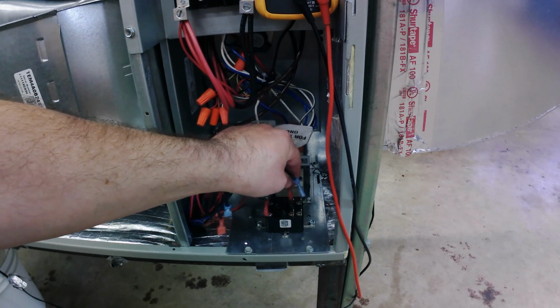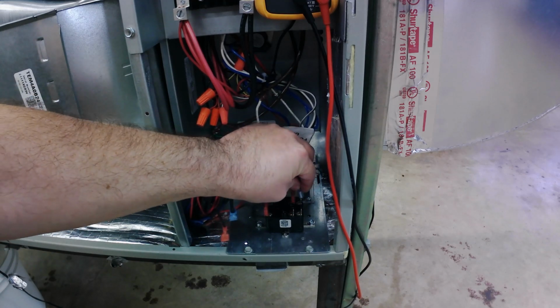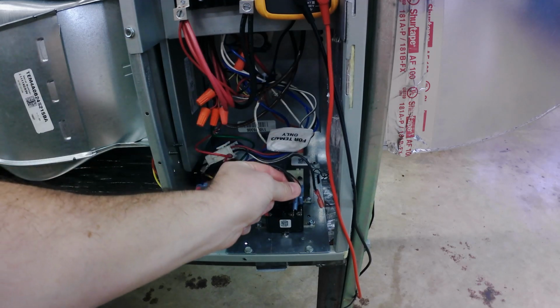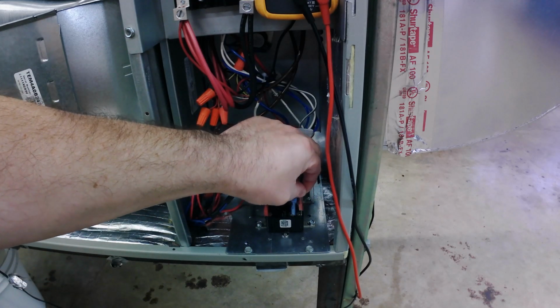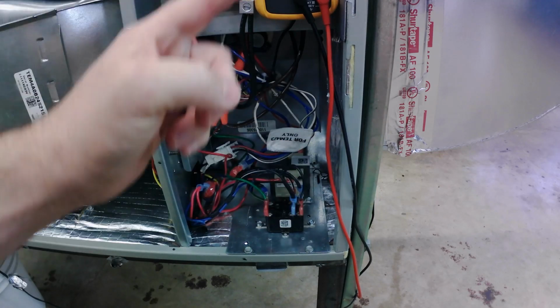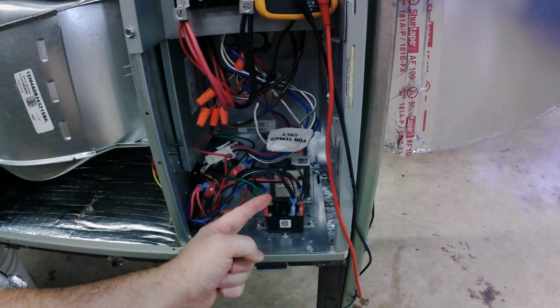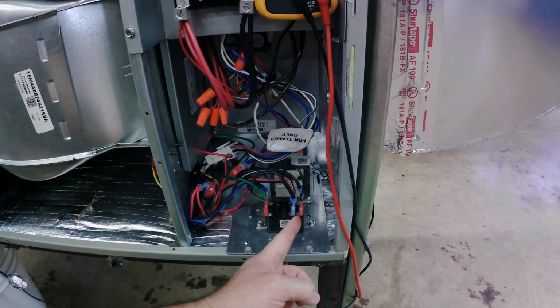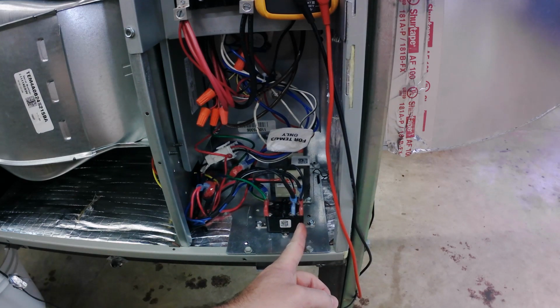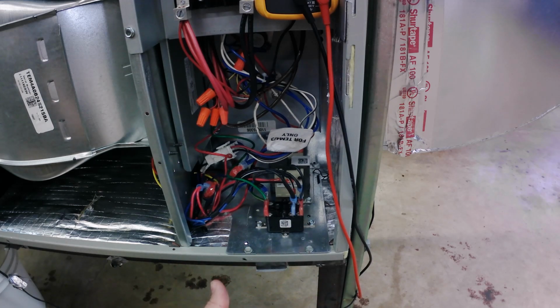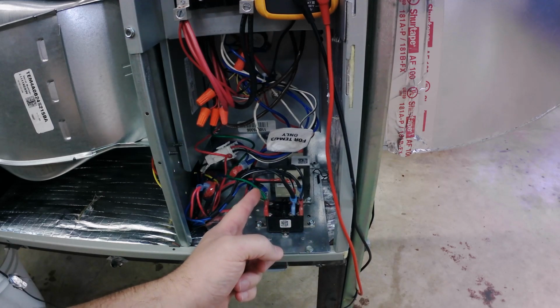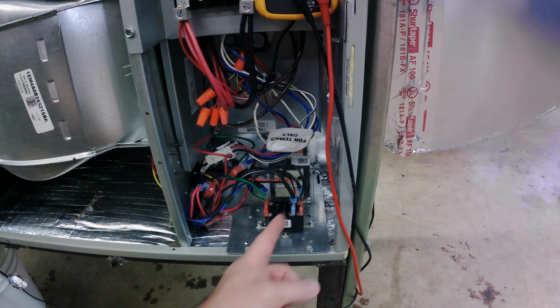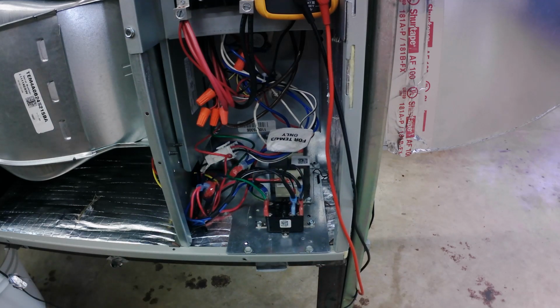So, I mean, there's a couple ways you could do it. If you're familiar with the voltage on the switch, or if you have to use voltage reference to the terminal block, however you do it, but know that the thermostat controls the coil. If there's a good coil there, then that coil is going to control the normally open and normally closed switch in this case. Some relays only have one or the other, or some relays have both, or multiple sets of both. So make sure that the thermostat controls the coil, the coil controls the switch, and in this case, once the switch passes power out, we've got a PSC motor in our unit here.